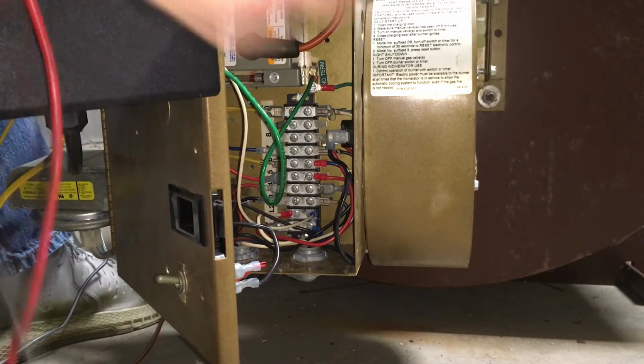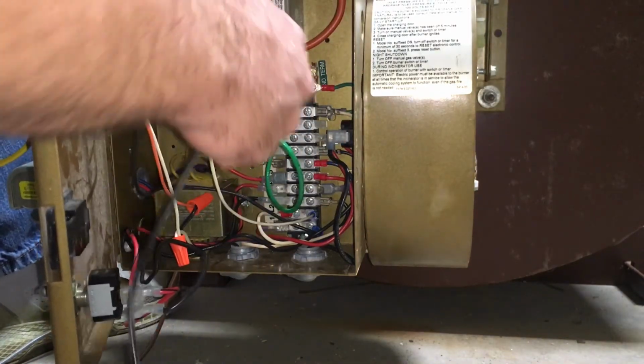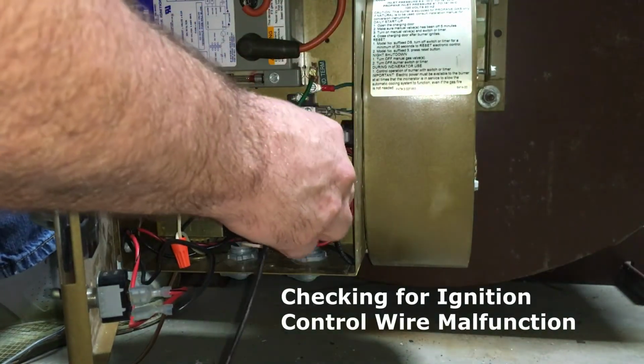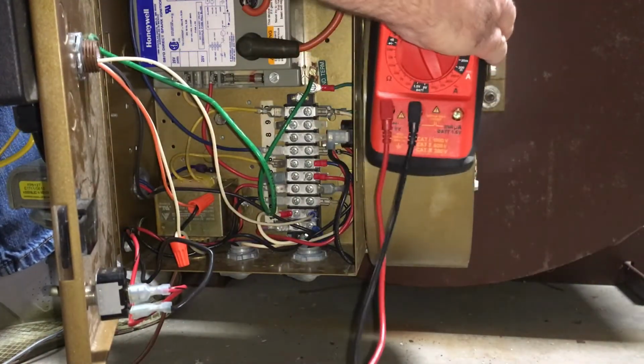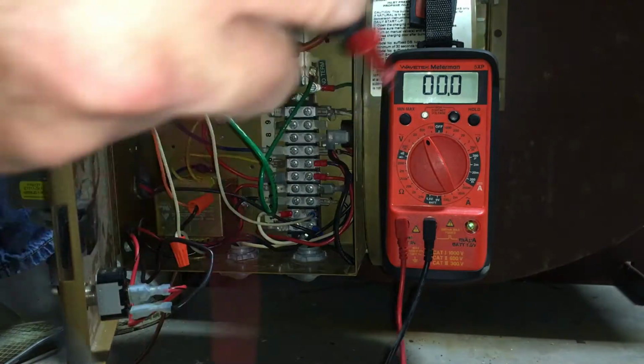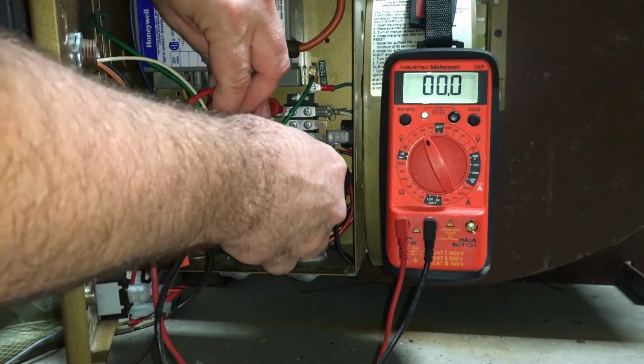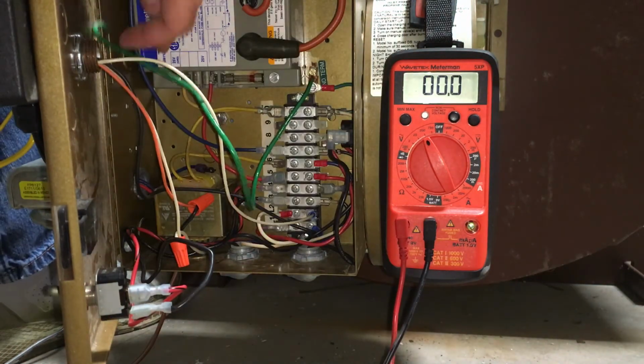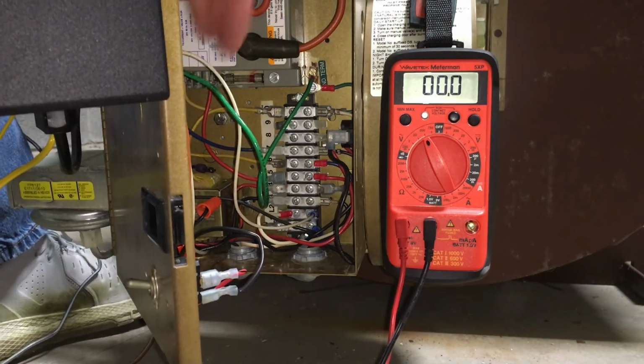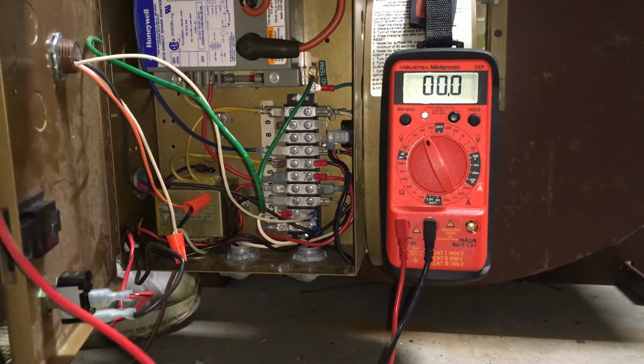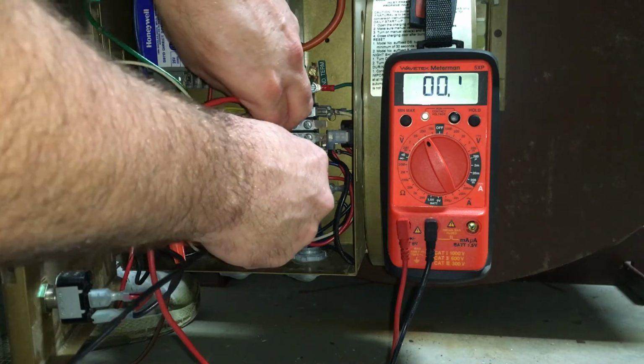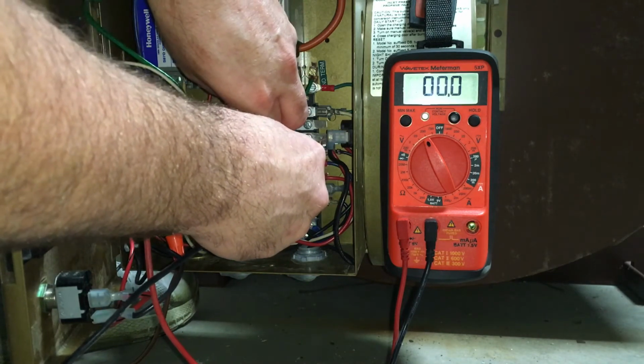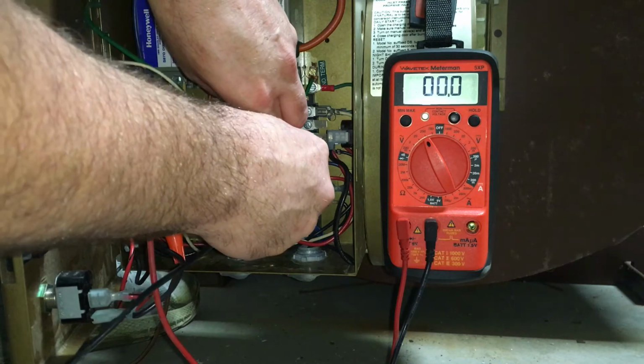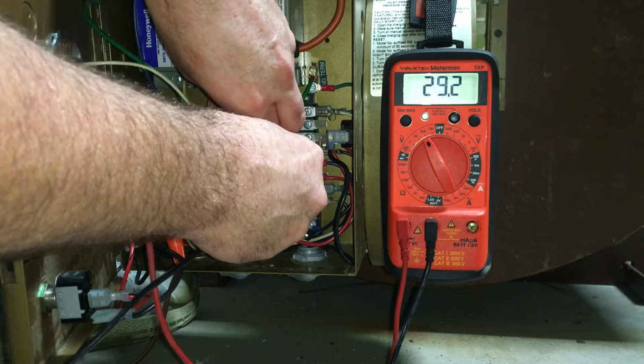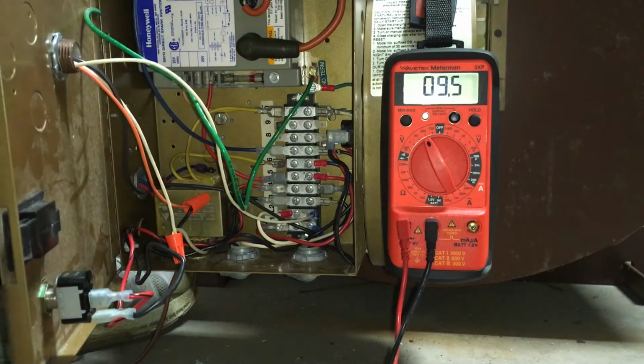Now we're going to check if this blue wire coming from the ignition control is faulty or not. So you would check between terminal 7 and 10. Put my meter up there. Between 7 and 10, we're not getting any voltage. Again, it's acting as if maybe this wire is bad, so make sure it's got good connection. Replace the wire. Turn it back on. Ignition just kicked in. So yes, we were getting proper voltage, so replacing that wire took care of that issue.